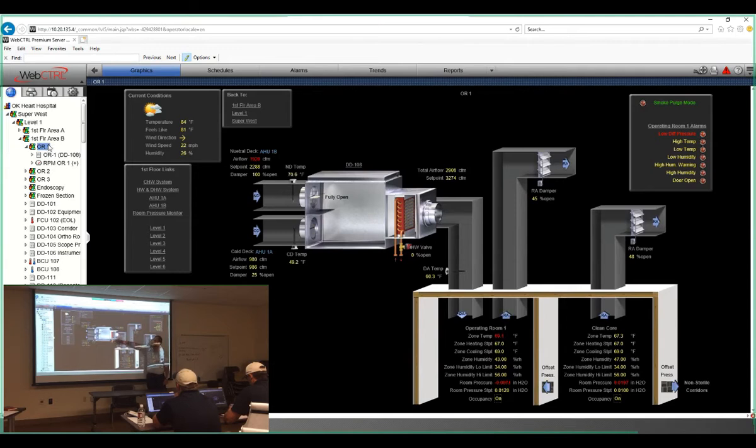The cold deck is strictly for cooling, so the more we get a call for cooling, the more this set point goes up. When it goes up, we subtract that from the 3275, and that's what the neutral deck is trying to produce. Make sense? If we were at full cooling, and this was doing 3275, the set point on the neutral deck would go to 0.